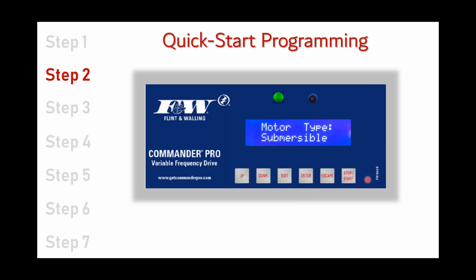And once you do that, it's going to ask you about these motor types. Again, we need to make sure the drive is programmed for a 1.5 horse if you're using a 1.5 horse, so we're going to walk through this just to make sure that the folks back at F&W programmed it up properly. If you bought the drive separately and you're putting it on some other pump, we're going to walk through this too.